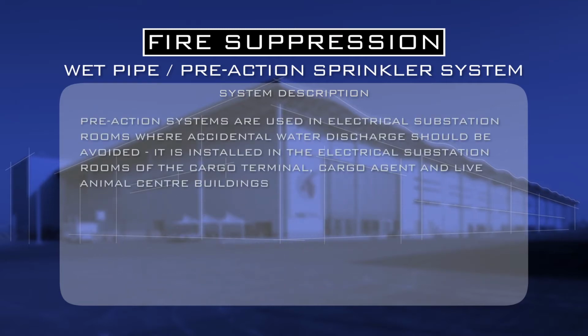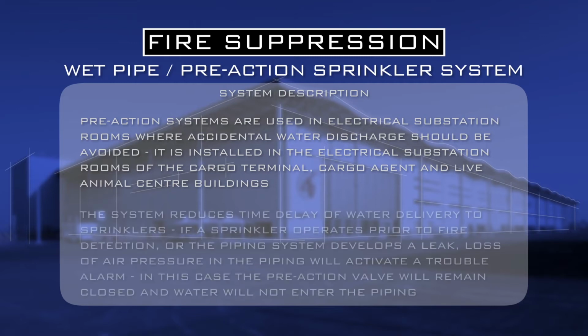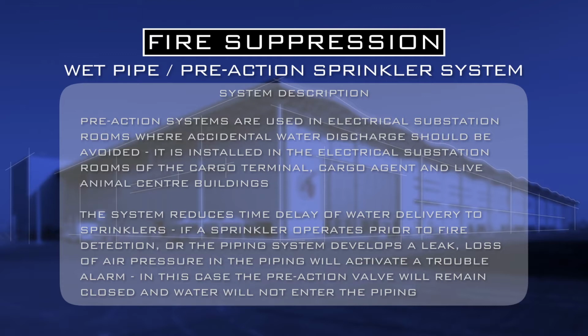Pre-action systems are used in electrical substation rooms where accidental water discharge should be avoided. It's installed in the electrical substation rooms of the cargo terminal, cargo agent, and live animal centre buildings. The system reduces delay in water delivery to the sprinklers. If the sprinkler operates before a fire is detected or the piping system develops a leak, loss of air pressure in the piping will activate an alarm. In this case, the pre-action valve will remain closed and water will not enter the piping.